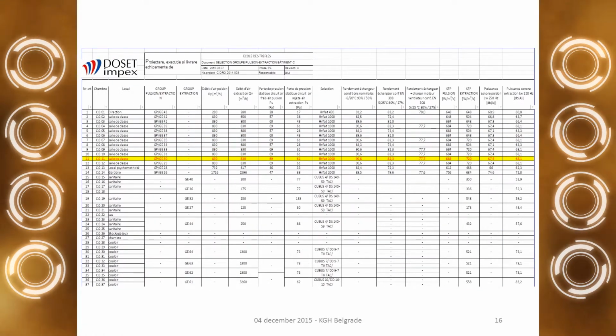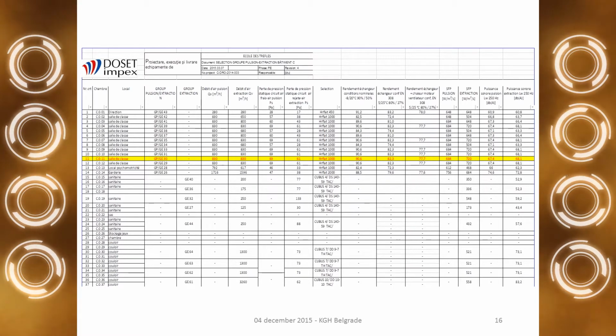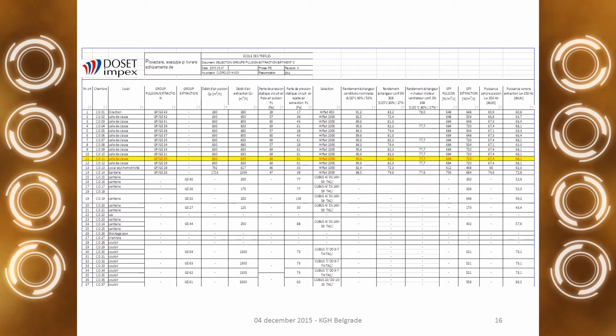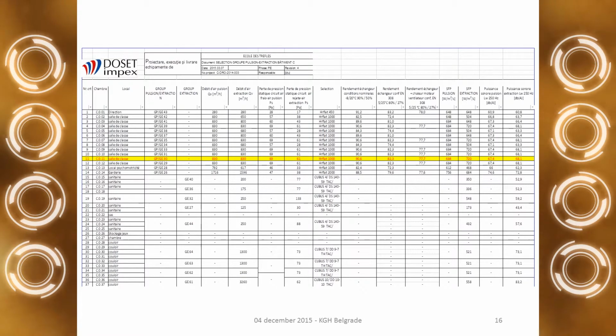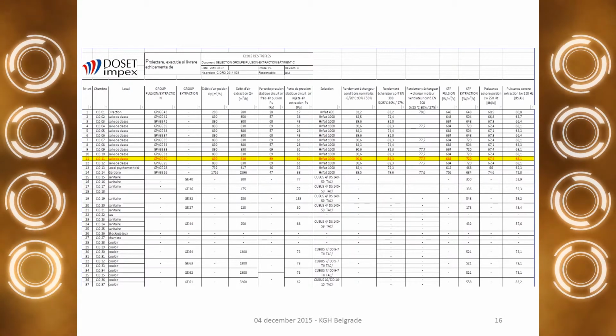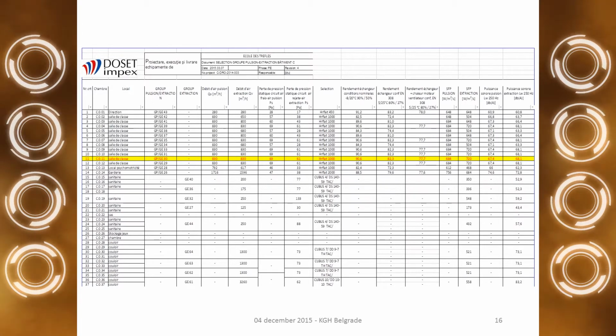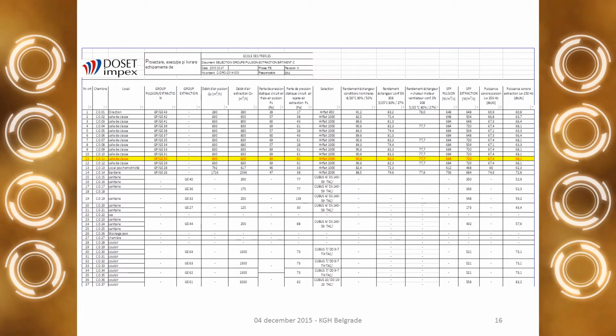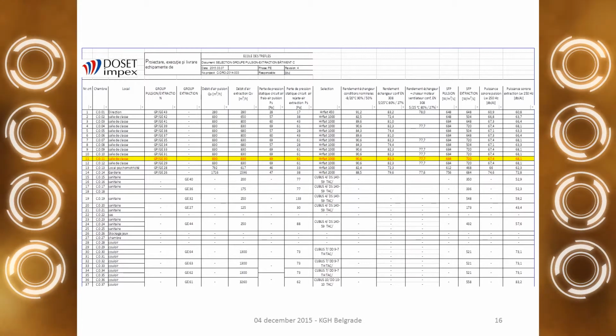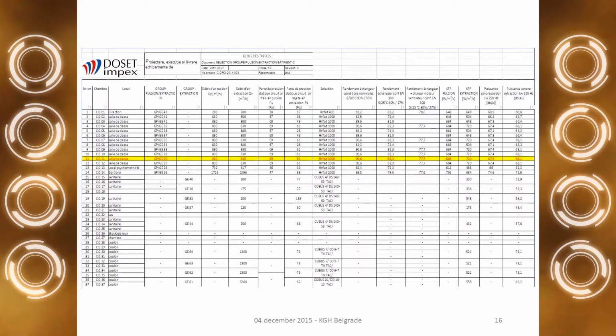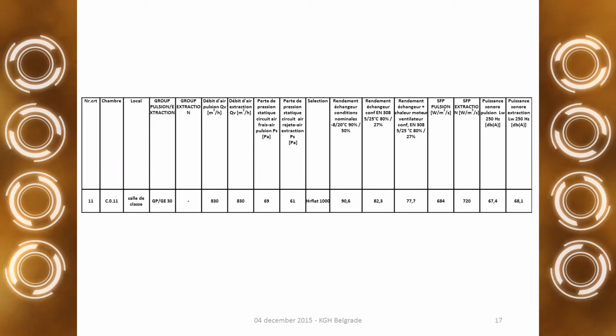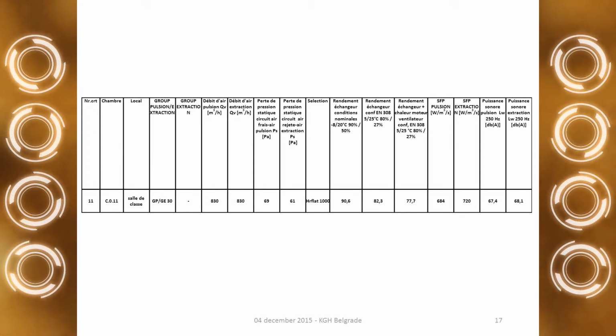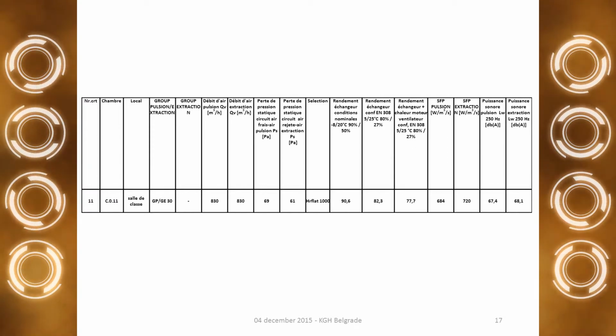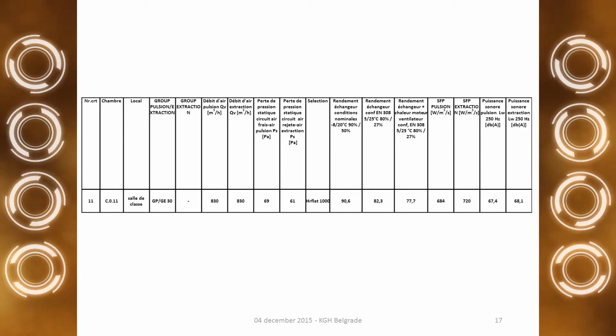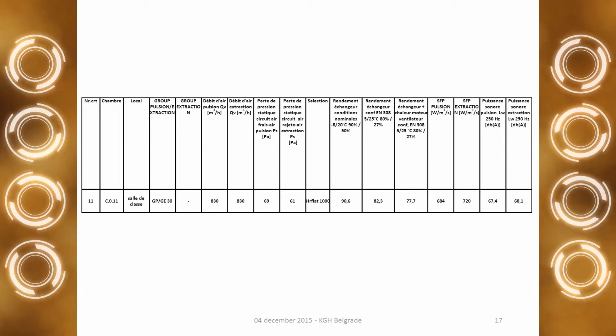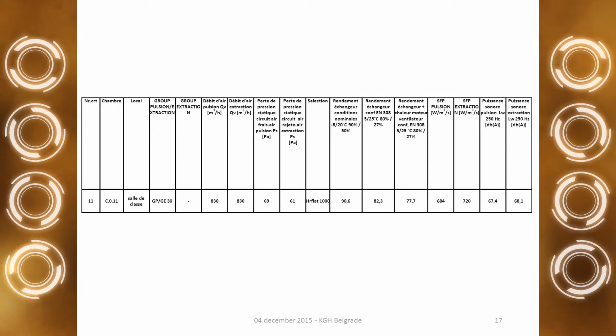An important parameter which we should prove, measured on site, was the specific fan power characteristic, also for each fan, for supply and for extraction. In fact, what we have here in the table is the calculated specific fan power, which is 684 for supply and 720 for exhaust. The condition was to be in class 2, less than 750 watt per cubic meter per second.